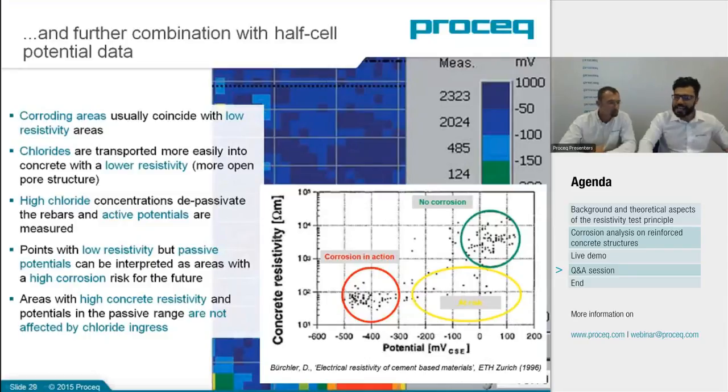Second question: is ASTM G57 for the 4 electrode test? There is a temperature correction chart. Is there the same kind of chart for soil in this test for concrete? Okay, now that's a tough one. I know we have it in literature. Just to let you know, these questions are coming from Iran. Generally, they come with tough questions. My God. No. Again, I know for sure, and I can probably provide some references based on literature.